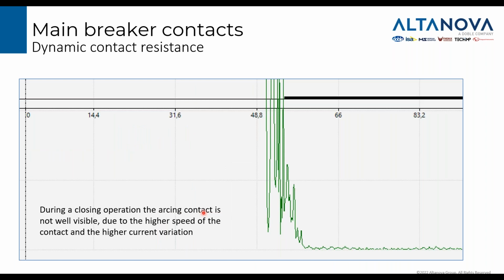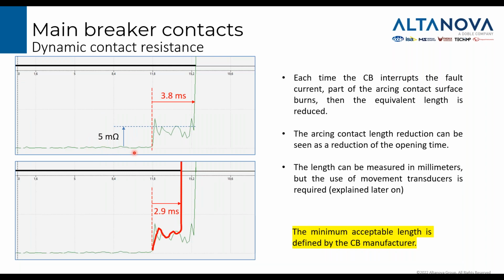All the examples that we have seen in the previous slides belong to the open operation. But when you try to do the same measurement when you close the circuit breaker, most probably you will not find a good graph as you can find during the open operation. The speed of the contact, first of all, is higher, because, let me go back to the previous slide. We start from the close position here, then here is where the contact starts moving. So we assume that the speed in this part of the operation is much less than at the end of the operation.